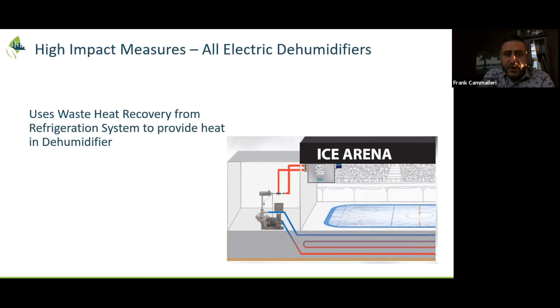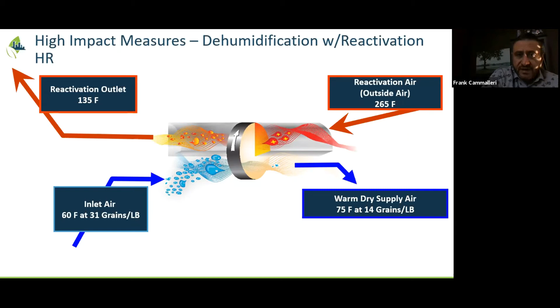Next slide. So this talks about dehumidification using reactivation. If you look at the top left corner, that's the temperature of the air that you have. On the exhaust side, that's the product of using a heated source to make that thermal wheel a lot more effective. But instead of discarding it out, we're trying to recover that, using a recovery coil to make use of that high 135 degrees to see if it can be used elsewhere. Okay, so next slide.